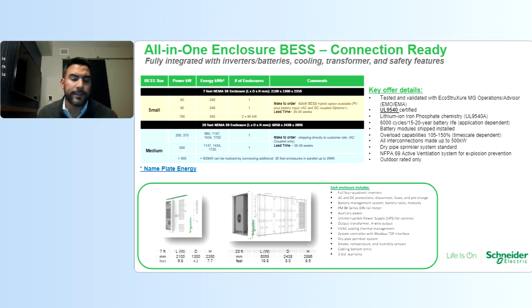But these are all in one. They come with the inverters, the batteries, the battery management system, the output transformer. They're specifically all in one. They're UL listed for 9540, which is the UL certification for energy storage systems, battery energy storage systems. And then also comes with the UL 9540A, the lithium ion thermal runaway listing as well. So in the event of a thermal runaway, that's compartmentalized and kept within each section respectively.